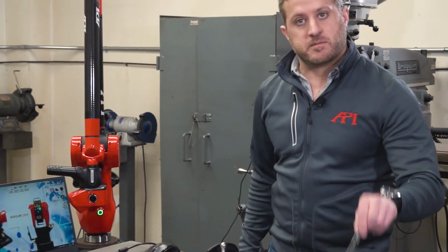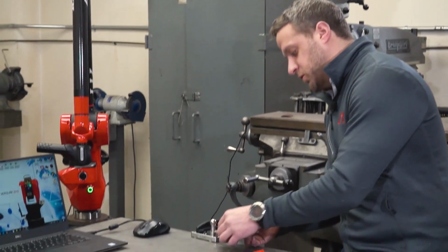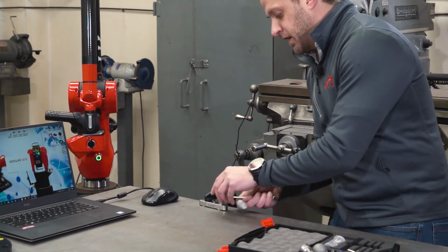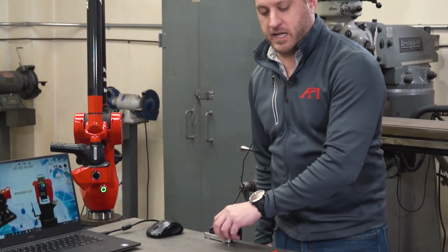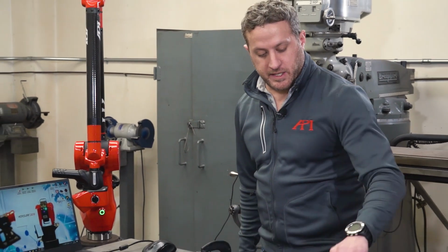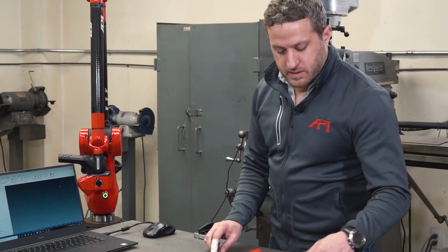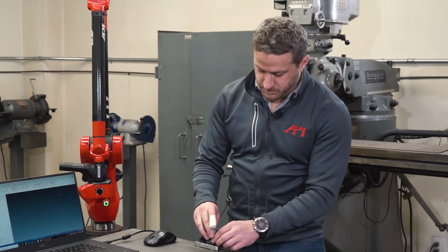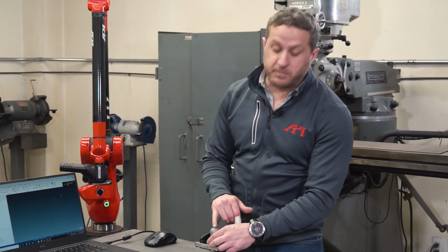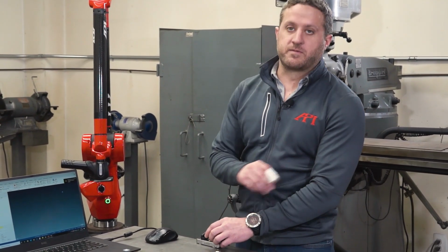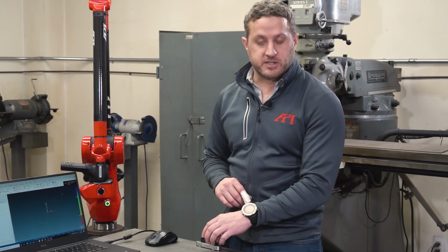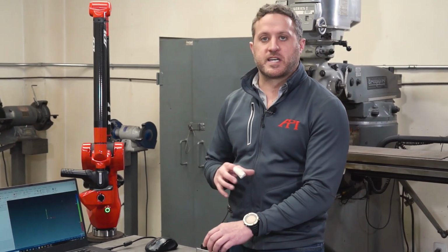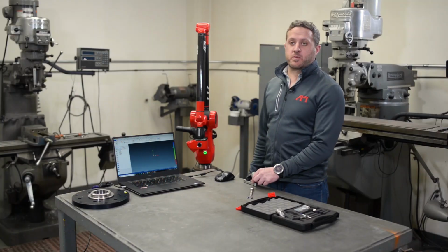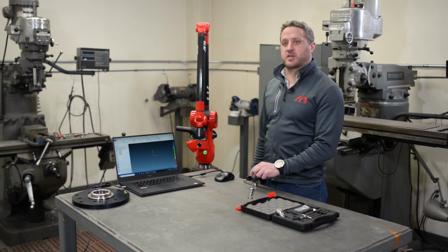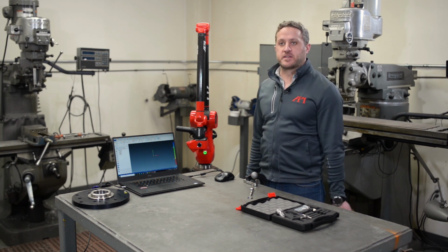Also, while that's firing up, I'm going to take my tool, and I'm going to remove the sphere that we use to calibrate the probe, and we're going to install the matte looking sphere. So the scanner needs a different type of sphere because the reflectivity of the other sphere messes with the calibration results. So this sphere was specifically manufactured for the calibration of this scanner.